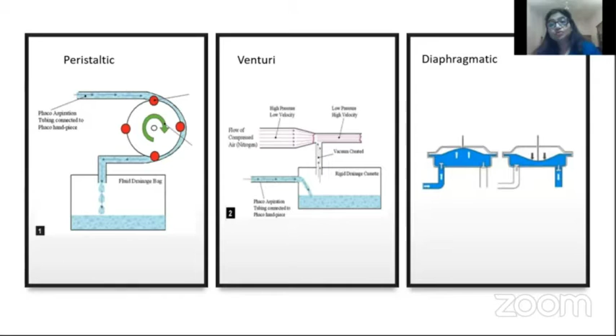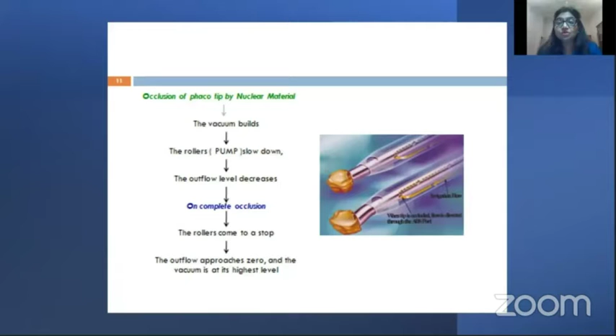And once the tip is occluded by the nuclear fragment, the vacuum starts building. The rollers slow down. The outflow or the aspiration level decreases. And on complete occlusion, the rollers come to a complete stop and the outflow approaches zero. And this is the time that the vacuum is at its highest. And once this tip gets occluded, you will hear that ting, ting, ting, ting sound on the machine, which means there is complete or total occlusion. And then you can use your phaco power.